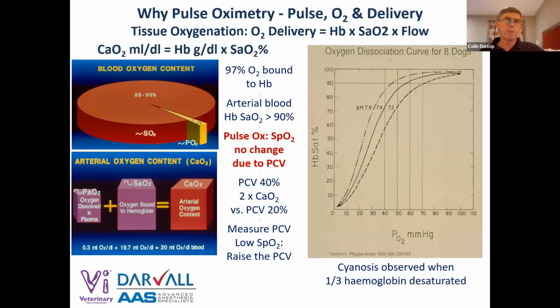What is it trying to do? 97% of the oxygen is carried on red cells. So the first thing is that we're trying to measure the oxygen on those red cells. So we're looking at the light absorption through the blood to try to understand the oxygen on the red cells. The relationship between the oxygen partial pressure and the hemoglobin saturation is shown on that graph on the right. It's an exponential relationship. And what we're interested in is where the graph goes flat at the top, which is above the 90% line. And that's what we would consider to be arterial blood, because we can run around the block now, have changes in the oxygen level in our blood, and we don't fall down.